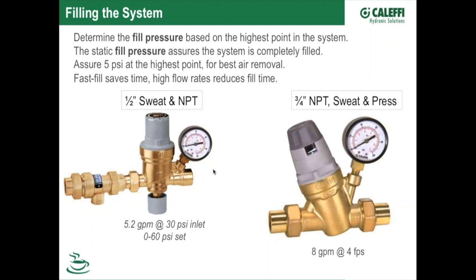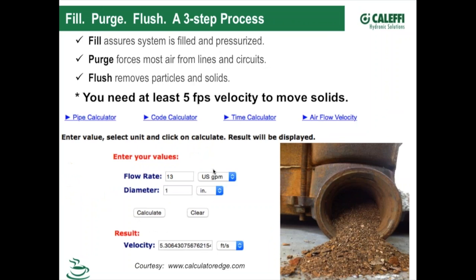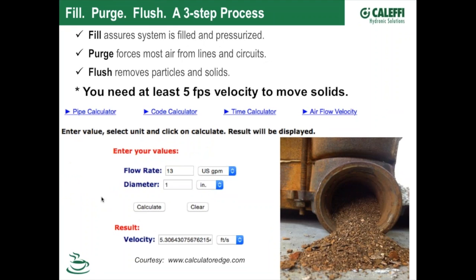I kind of consider that process, that filling and purging, a 3-step process. We fill it, which means we get it up to the static fill pressure that we need to lift the water up into the system. Then we purge it. We hook a hose somewhere on a valve, and we allow the air bubbles to be forced out as the water's filling the system. That makes sure when we start up our pumps that we're going to get circulation through the system.